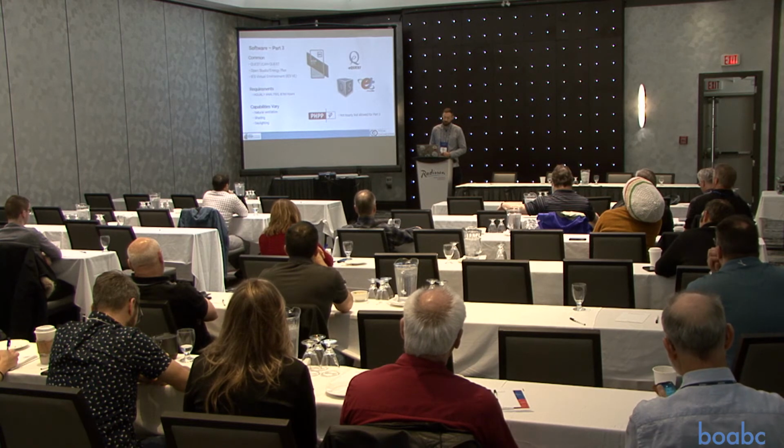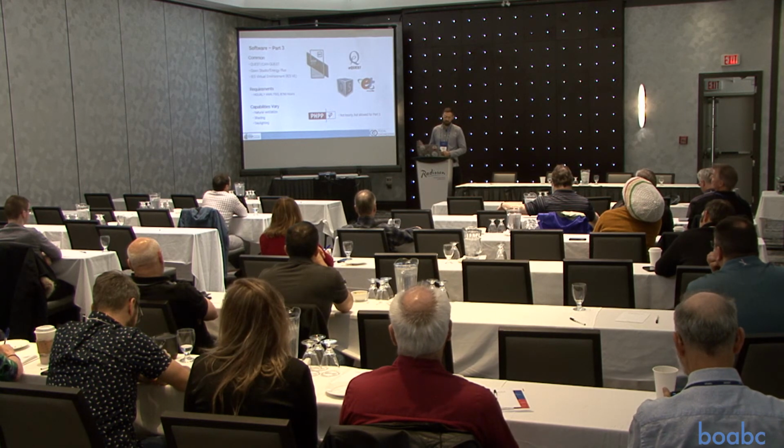We use Flixo. Yeah, so there are generally two software packages for evaluating the heat transfer through an envelope detail. They're two-dimensional finite element analysis heat transfer software, kind of fun to use. THERM is free. It's totally sufficient. It's a bit clunky to use. Flixo is reasonably priced, and it's a much nicer user interface. Produces great results. That's the example I showed you earlier of that window detail.